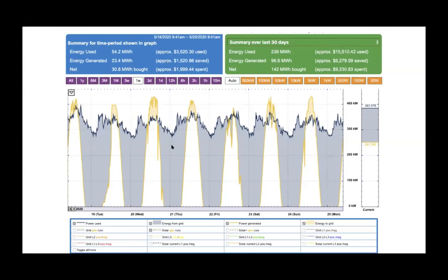I mentioned the phantom and ghost loads. I discussed that a little bit earlier in a slide. Those are loads where you just aren't quite sure where that power and energy is being used. And then power factor is useful to know, because a lot of times the building has to be within a certain threshold of power factor for the utility to provide quality power to that building. Each of these elements that I've just briefly gone over can impact energy efficiency. If issues or trends are identified, then corrective measures can be taken to realize an environmental and financial benefit.